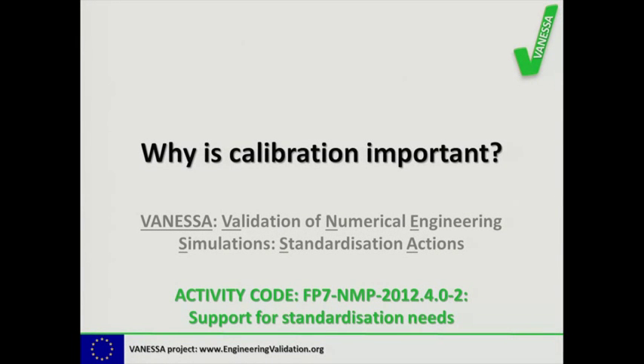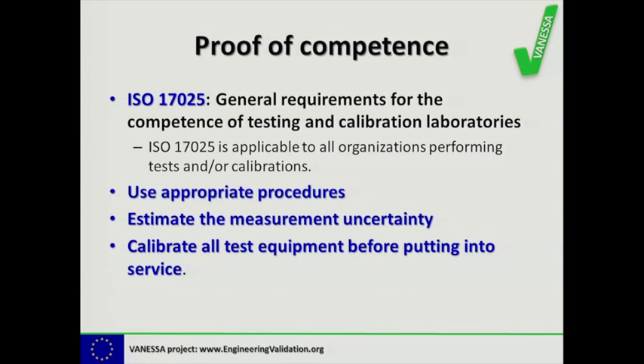Why is calibration important? There are several reasons. First, calibration is a proof of competence. The ISO guide 17025, which describes the general requirements for the competence of testing and calibration labs, is applicable to all organizations that perform tests and calibrations. This guide tells you that you should use appropriate procedures, estimate the measurement uncertainty, and calibrate all test equipment before putting it into service.